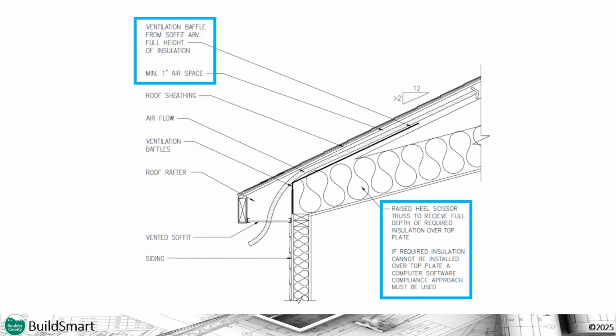I wanted to show you an attic scissor truss and a detail on the Colorado Energy Office's website because you not only have to consider insulation over the top plate and heel height, but if you are installing ductwork in the attic, you will need to consider how much height you have to maintain the R value of the insulation with the duct that might be installed near the exterior wall where the heel height is at its lowest point, meaning that the design team may need to increase the heel height in the raised heel truss even more to properly accommodate insulation and ductwork.